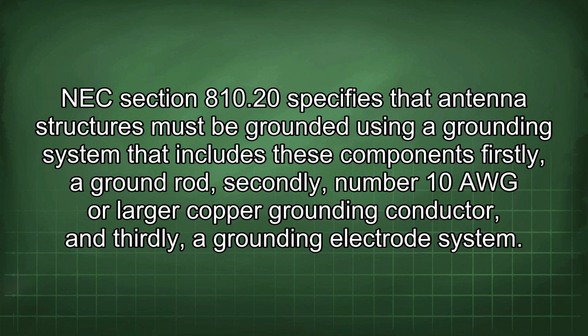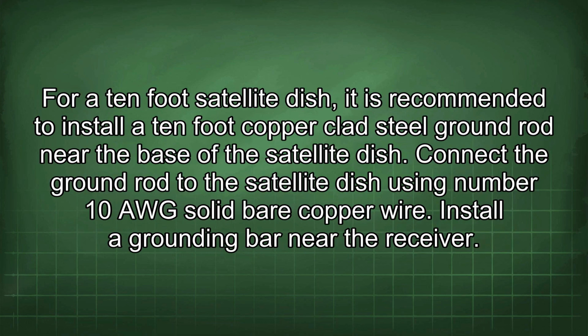NEC Section 810.20 specifies that antenna structures must be grounded using a grounding system that includes these components: firstly, a ground rod; secondly, number 10 AWG or larger copper grounding conductor; and thirdly, a grounding electrode system. For a 10-foot satellite dish, it is recommended to install a 10-foot copper-clad steel ground rod near the base of the satellite dish. Connect the ground rod to the satellite dish using number 10 AWG solid bare copper wire.